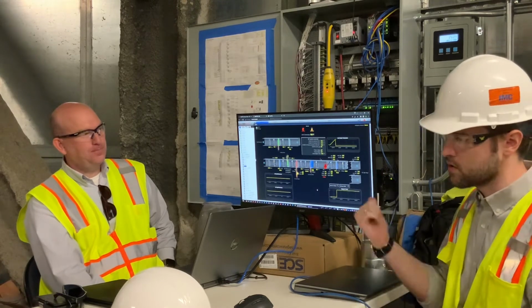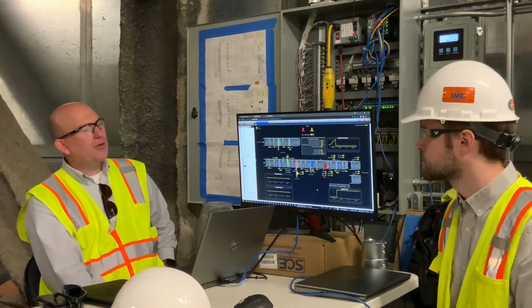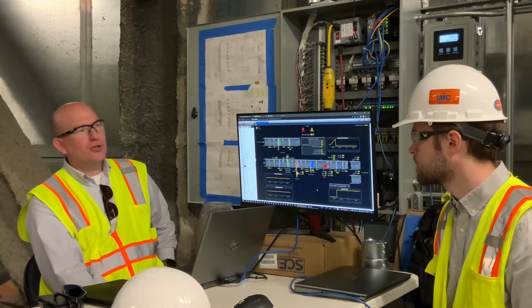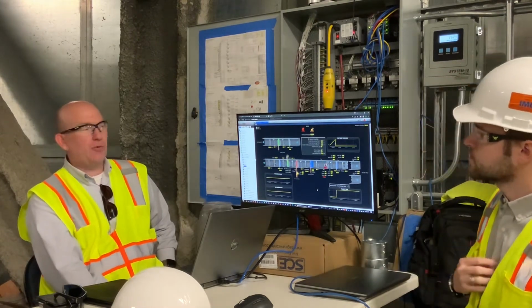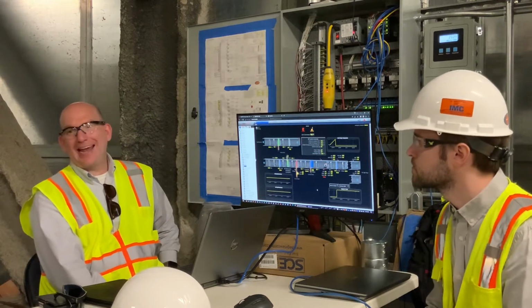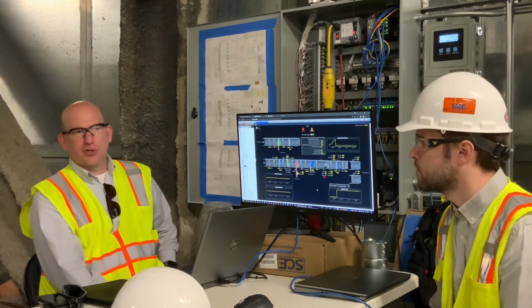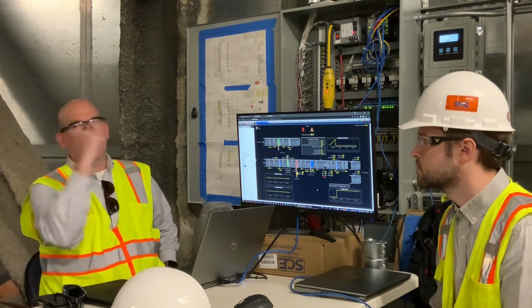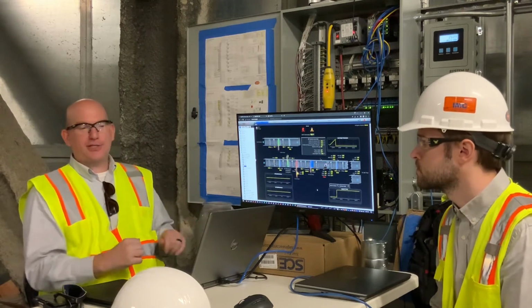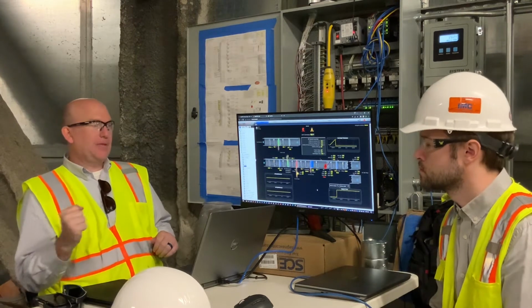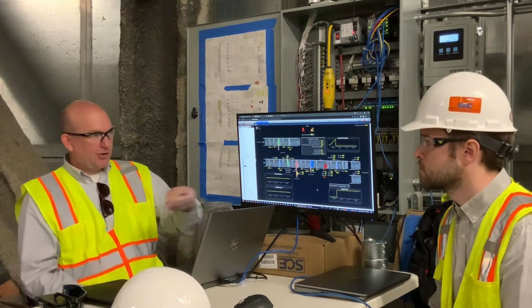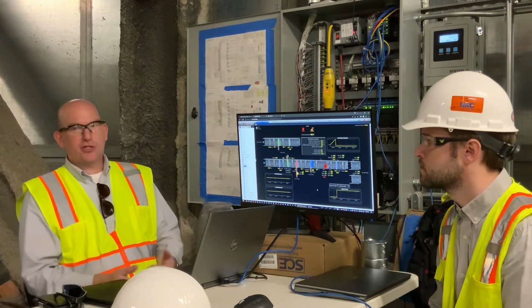That's a separate controller. Does the VFD on air handler 6 also control the damper? Yes. So that's another situation where if you did put the fan in hand, it should open the damper on its own. You shouldn't have to go to it and crank it. Worst case, you're walking around putting switches in hand and trying to get the air moving. You shouldn't have to crank the damper open; put the VFD in hand and it should also open the damper.